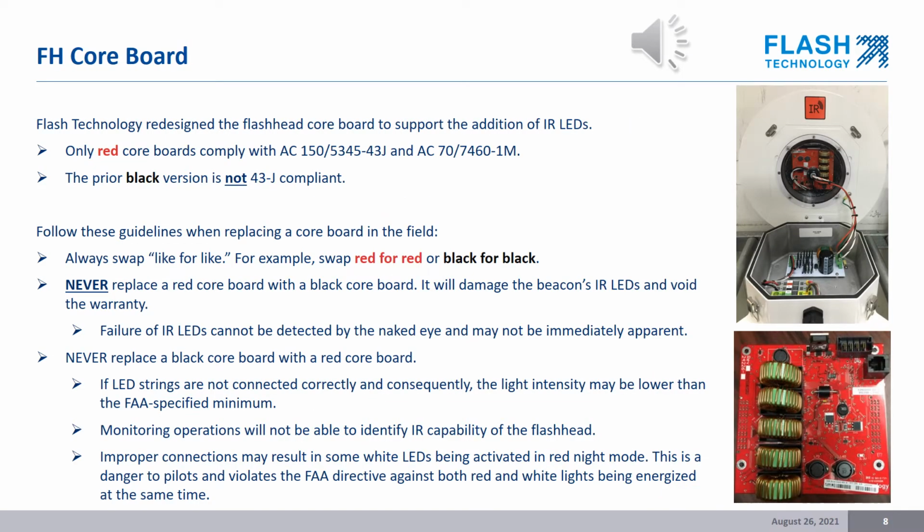Following the changes made to the marker structuring, an advancement was implemented for the flash heads. Flash Technology has redesigned the flash head core board to support the addition of IR LEDs. Only the red core boards comply with the AC 5345 43J and AC 7460 1M. The prior black version is not 43J compliant. Please follow the guidelines when replacing a core board in the field.